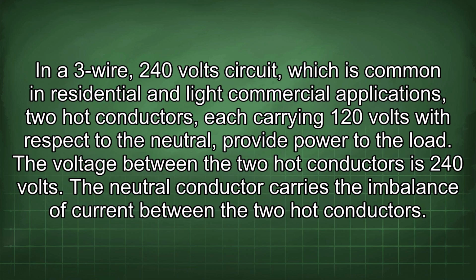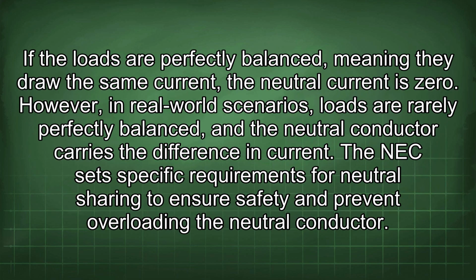In a 3-wire, 240-volt circuit, which is common in residential and light commercial applications, two hot conductors, each carrying 120 volts with respect to the neutral, provide power to the load. The voltage between the two hot conductors is 240 volts. The neutral conductor carries the imbalance of current between the two hot conductors. If the loads are perfectly balanced, meaning they draw the same current, the neutral current is zero. However, in real-world scenarios, loads are rarely perfectly balanced, and the neutral conductor carries the difference in current.